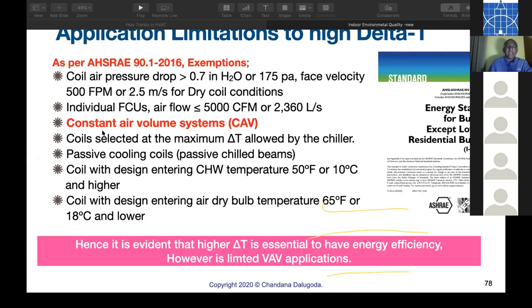They say constant air volume systems, no high delta T. So we'll have to find out why. I haven't gone through that. What are the difficulties? Why is it possible with VAV? It could be because it is a varying load. You have a varying load tackled by varying air. That is happening very, very closely. So that would be the reason.